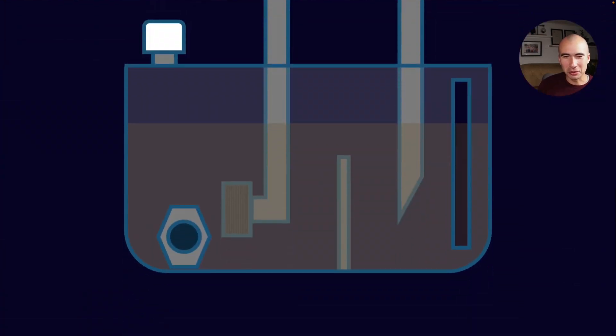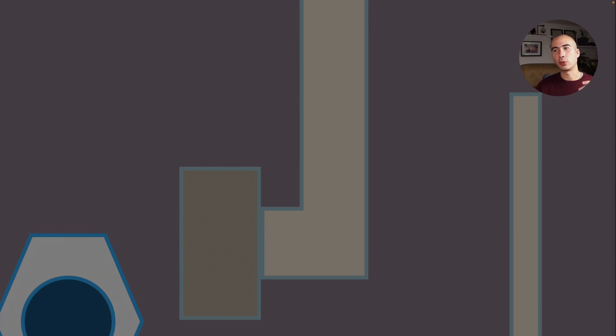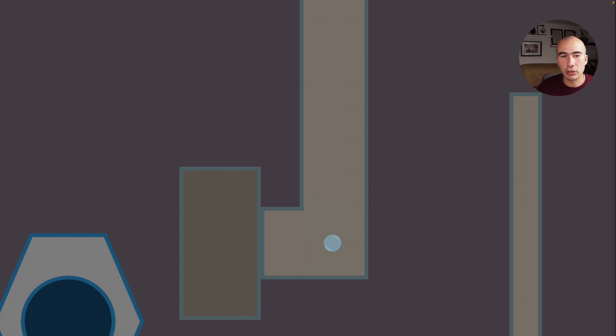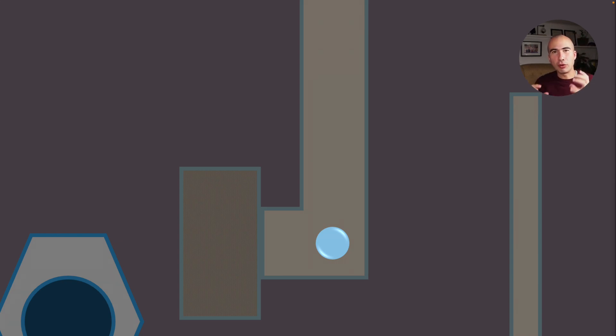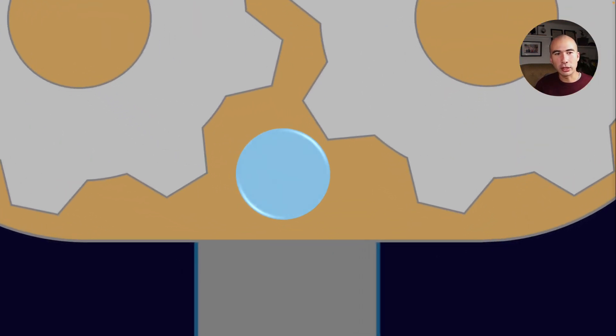How does this apply to our oil system? If we have some kind of restriction — at the breather, the strainer, or in the pipework — we are lowering the system pressure. If we lower the system pressure enough, we might have sufficient temperature to cause the boiling of water. If we have free water somewhere in our oil system and it encounters low pressure, there is the potential that it could boil, giving us vaporous water in our system — we no longer have free water, we have water vapors.